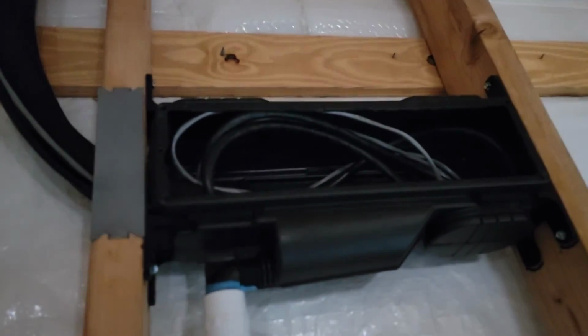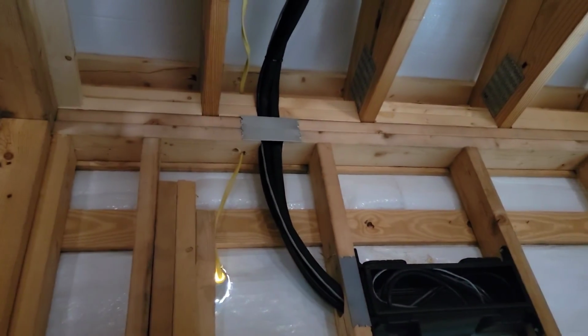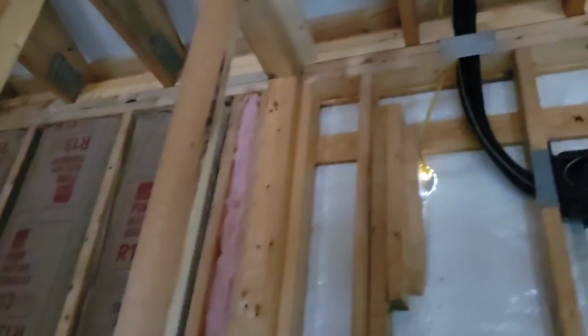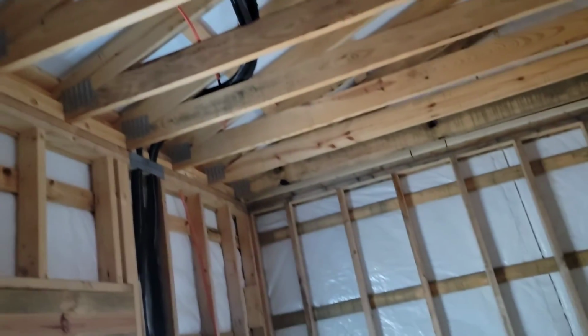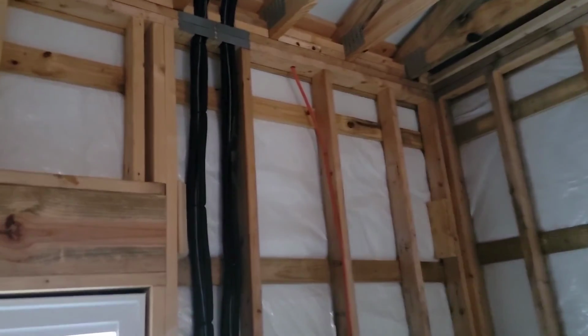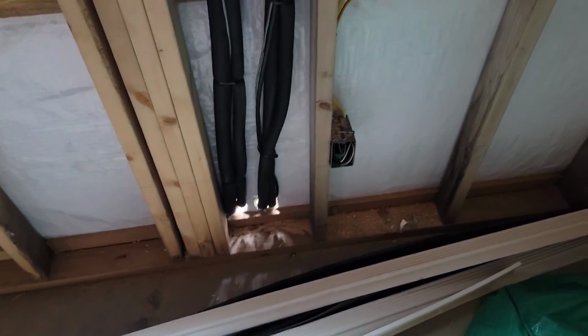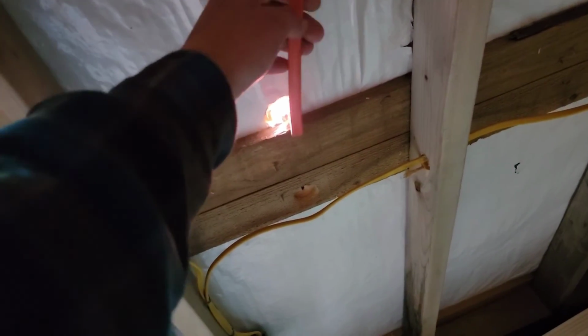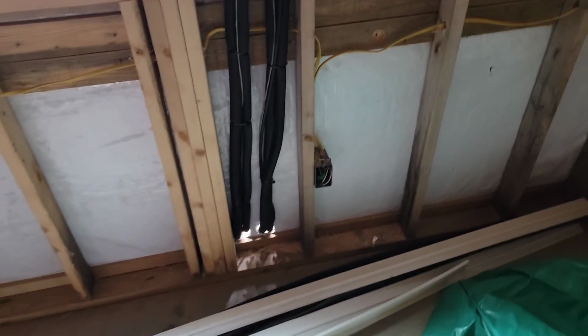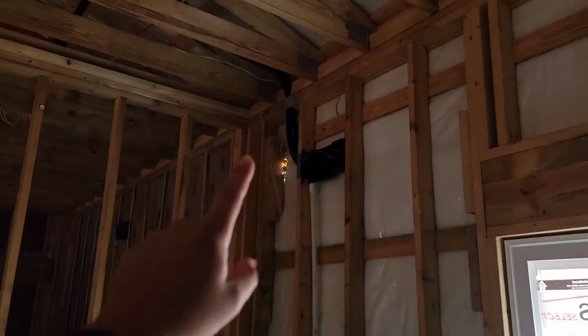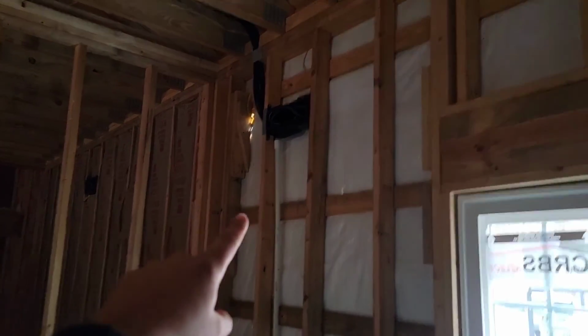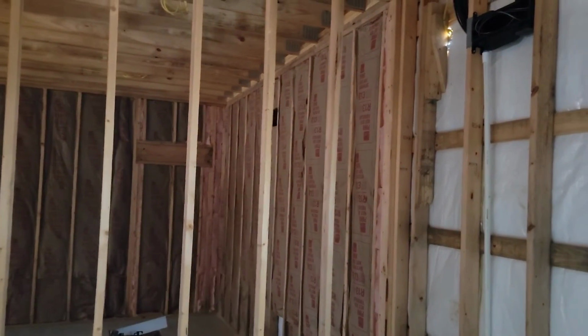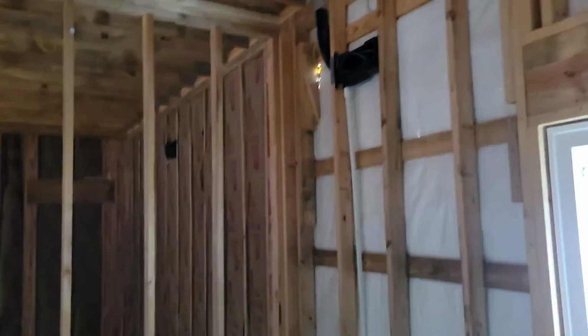Here it is, rough-in box. Drain goes down the wall and out, and the line sets go up. Why do line sets go up on both of these? That way we can run them over to where our outdoor unit's going to set outside, and it'll go down and out. And there's our wire for our 2-ton outdoor unit. We got 2 heads for that 2-ton outdoor unit. One is a 9,000 BTU wall mount air handler, and the other one is a 18,000 BTU air handler.